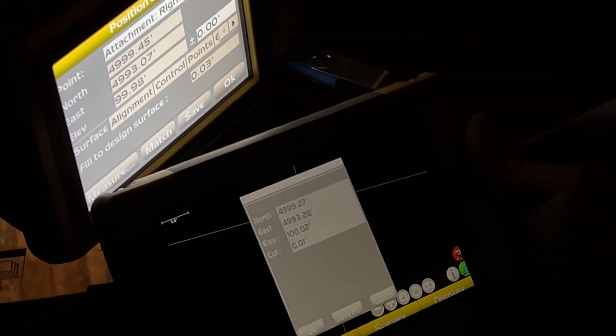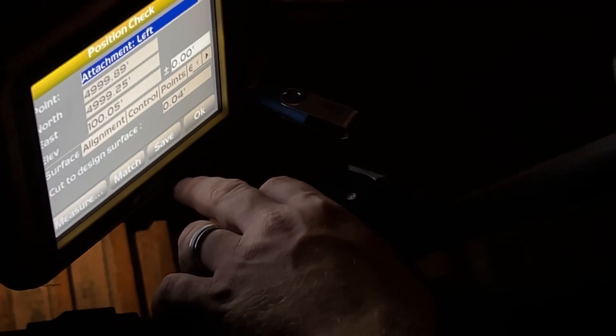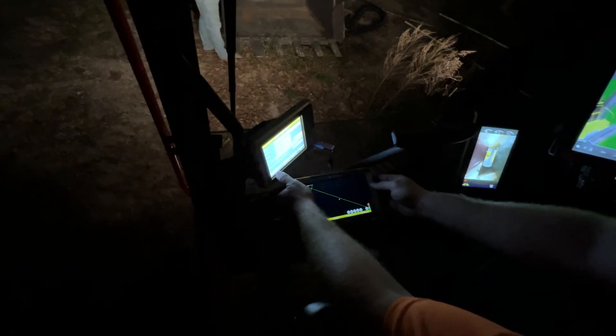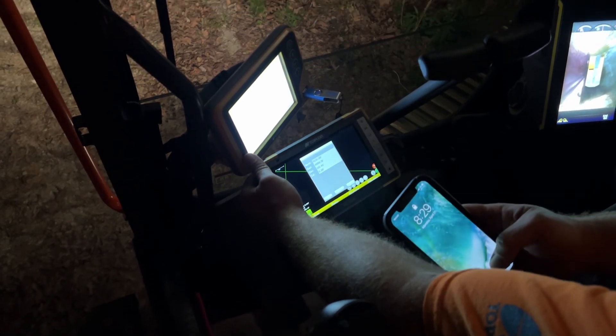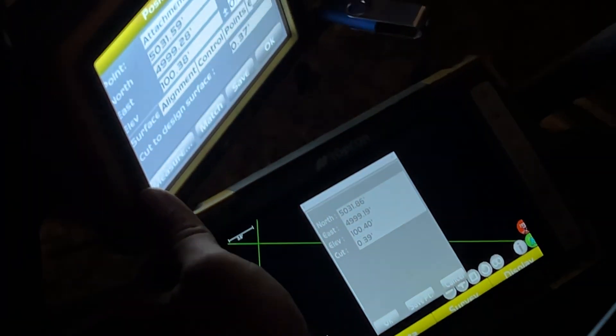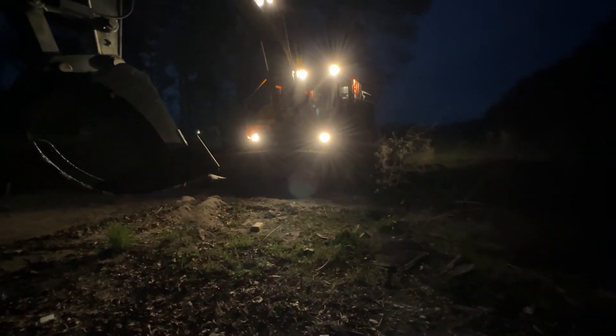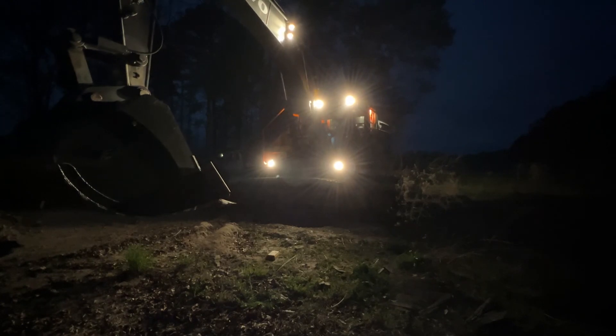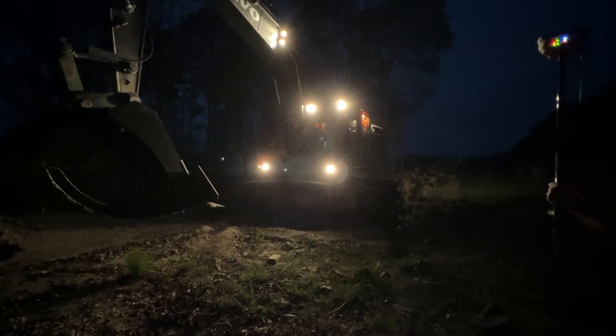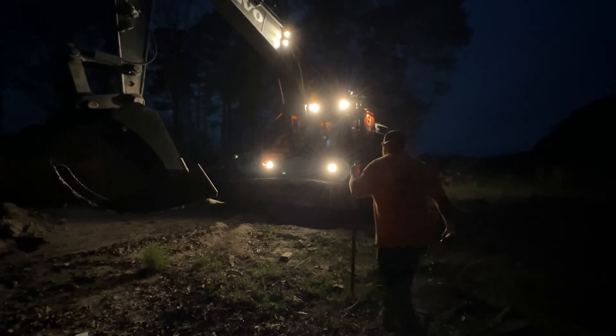Look at the numbers — you can see those numbers are within our calibration specs. I'm going to take a picture of it. Let's try the left side one time. We're so damn close. There you go — left shots. Looks good. Within a tenth elevation and three tenths northing and easting. Okay, we're good.